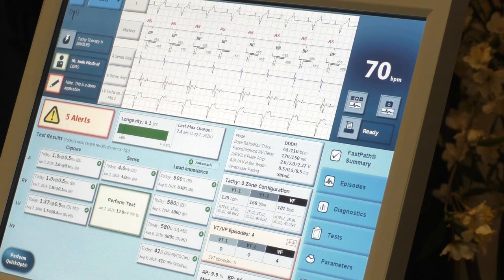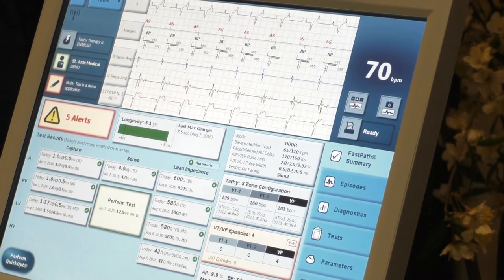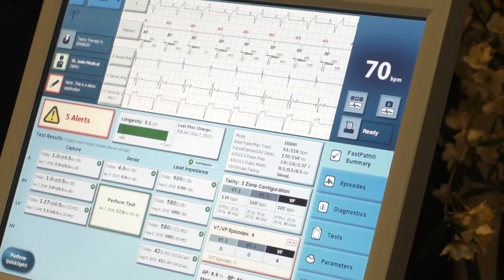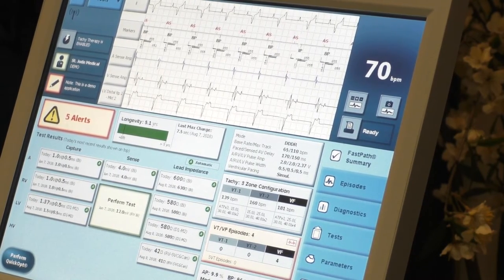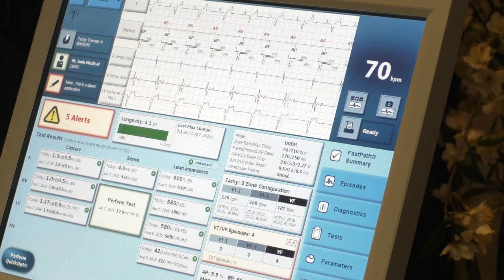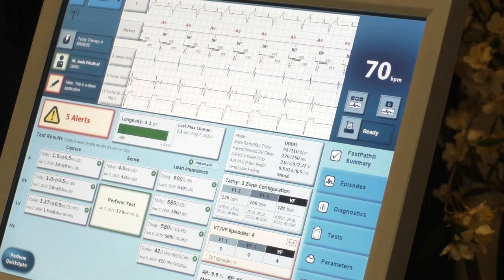If there's a hole in the insulation and electricity seeps out into the blood pool, will the impedance rise or decrease? Decrease — the impedance will drop. And the opposite is true: if the lead becomes kinked or the conductor fractures, or there's a total break in the lead, the impedance will rise to greater than 3,000 because the circuit cannot complete — there's a big gap in the circuitry.